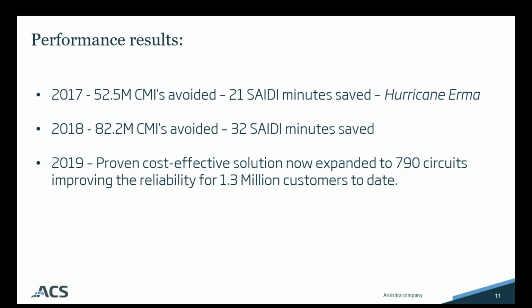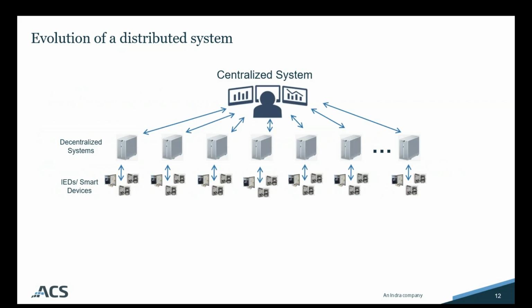Now, while we're very happy with the success and the expansion of this application, the key findings for our message today is that these controllers or servers sit architecturally and physically outside of the centralized DMS and work as a coordinated but autonomous system. The additional value this brings to a network is resiliency and reliability, as these systems can act as independent nodes operating within selected portions of the grid. They can also more efficiently process large amounts of data more locally. The logic, the rules, the system modules are located in multiple dedicated servers. They collect data, they make control decisions, and they issue commands to SCADA.